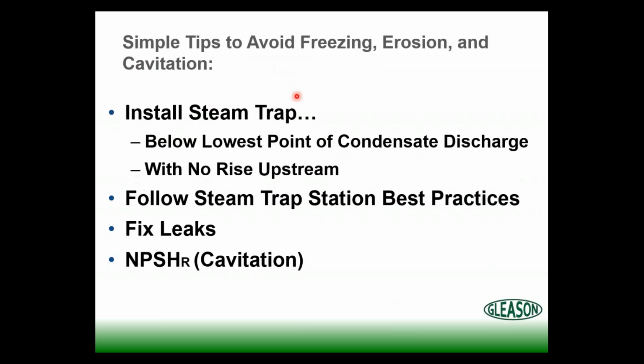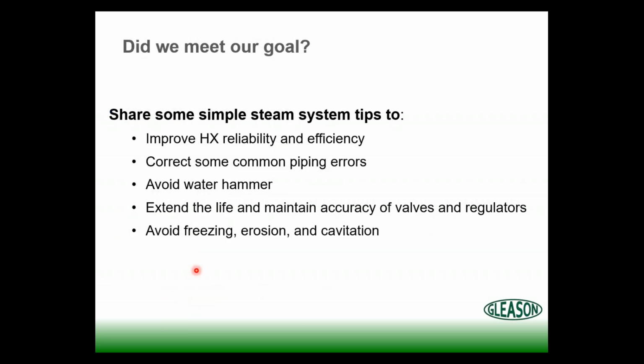So how to avoid freezing? Install steam traps below the lowest point. No rise upstream of the trap. Follow the steam trap station best practices. Fix your leaks. And please pay attention to NPSH required.